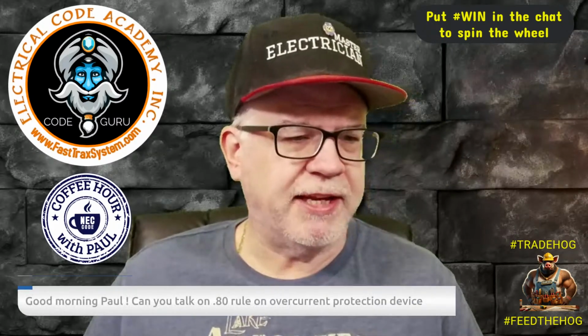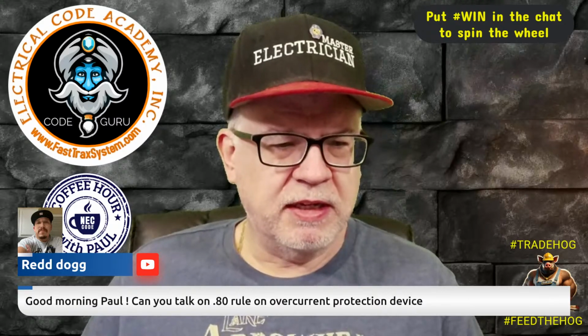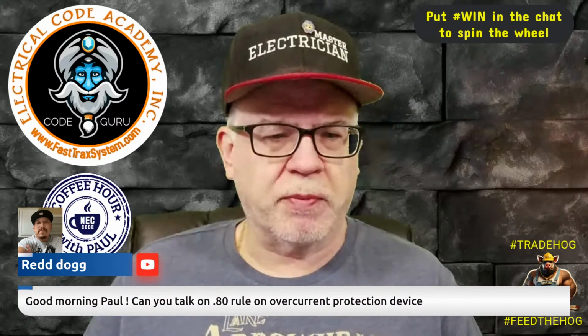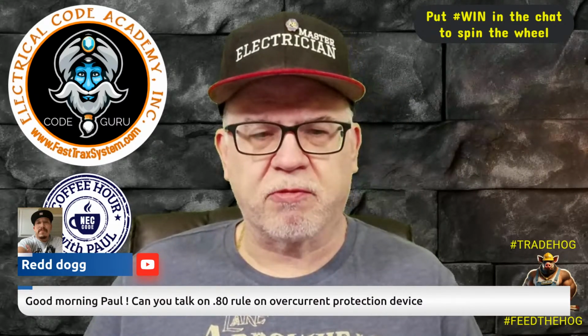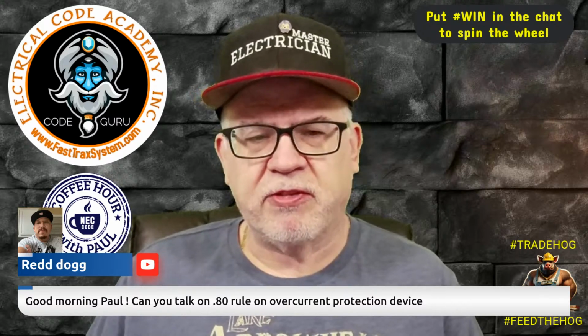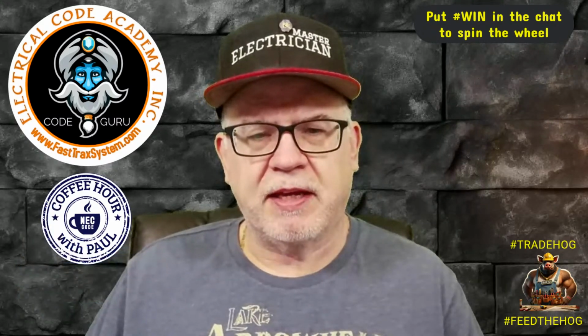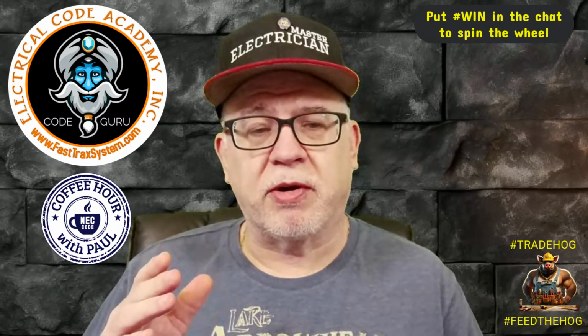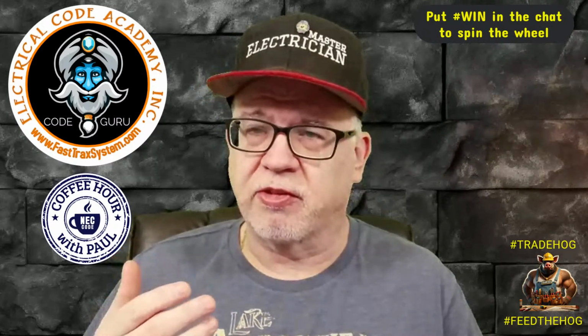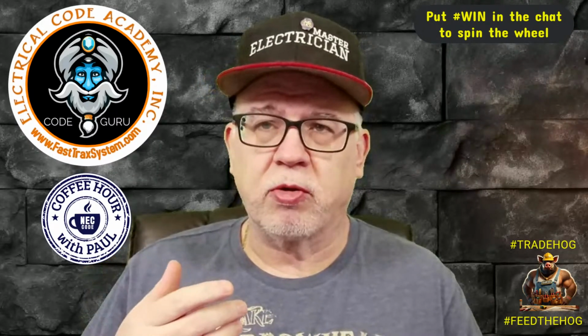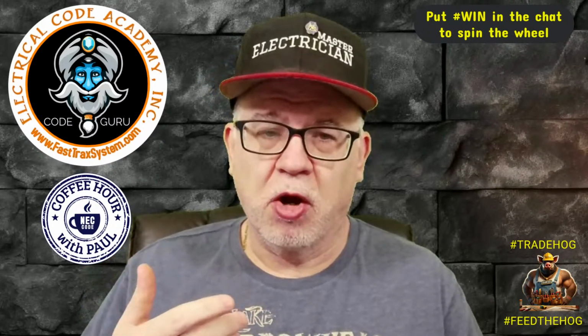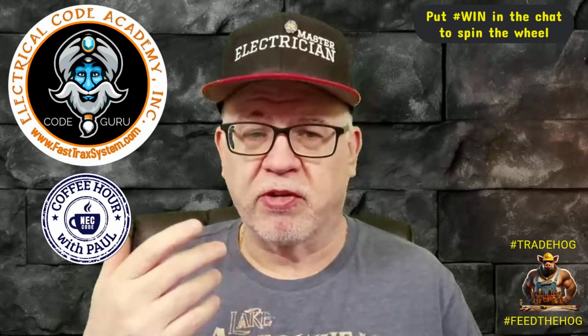Let's see here. Red Dog is in the house. Can you talk about the 80% rule for overcurrent protection devices? There's really no 80% rule. It's basically, if it's a continuous load, a normal circuit breaker is not rated for continuous loads. So what you do is you use 80% or you use the 125%. So they're reciprocal.